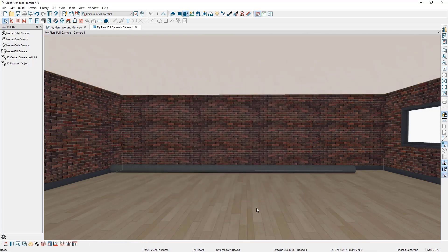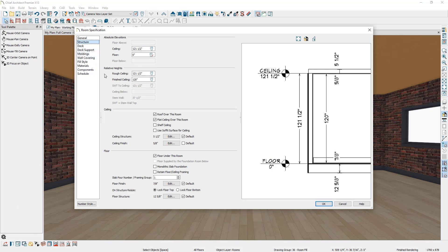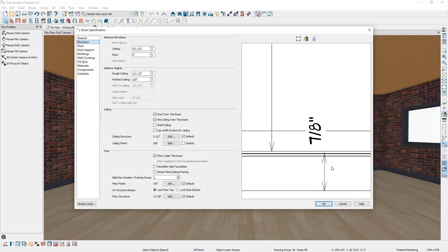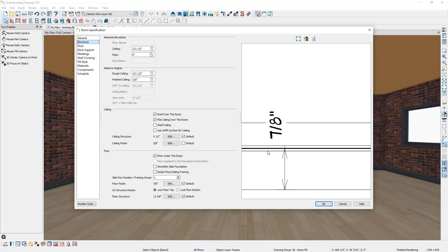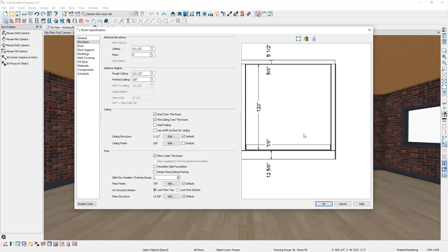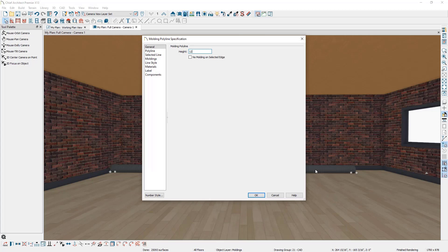Cancel the dialog, click in the room, and in the bottom left corner click Open Object Specification. Go to the Structure panel — the finished ceiling value, which is the room height, is 120 inches. The floor finish is 7/8 of an inch, measured from the top of the subfloor. So from the top of the subfloor to the top of the finished ceiling is 120 and 7/8 of an inch. Double click the duct, enter 120 and 7/8 into the Height field, then subtract the duct height of 12 and 3/8 of an inch to account for the bottom of the duct.